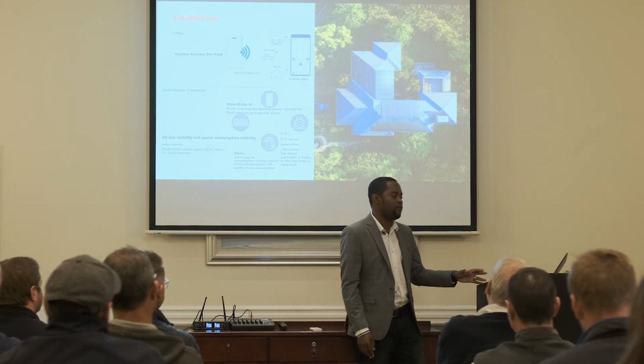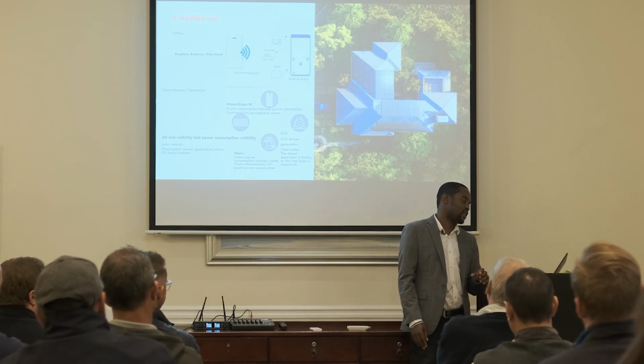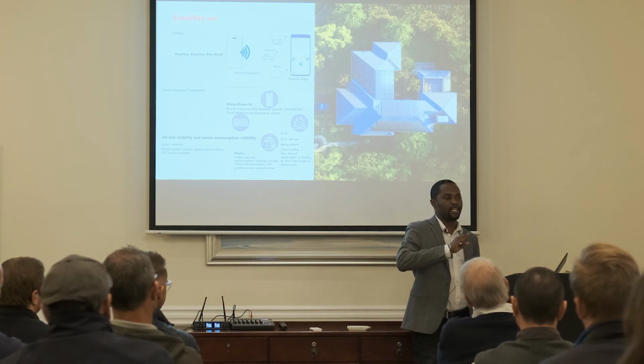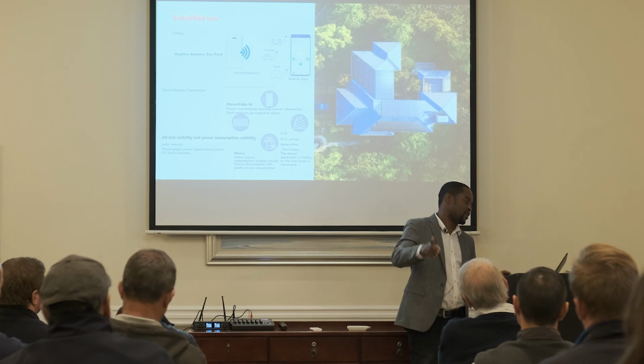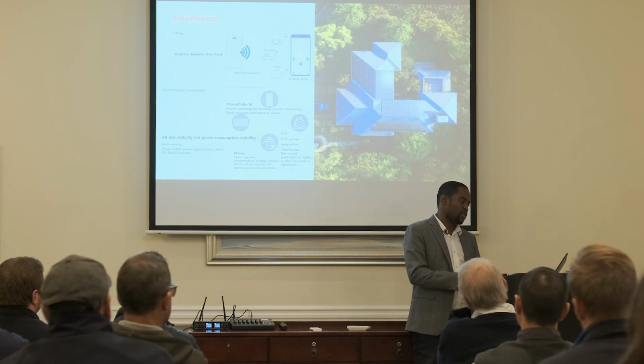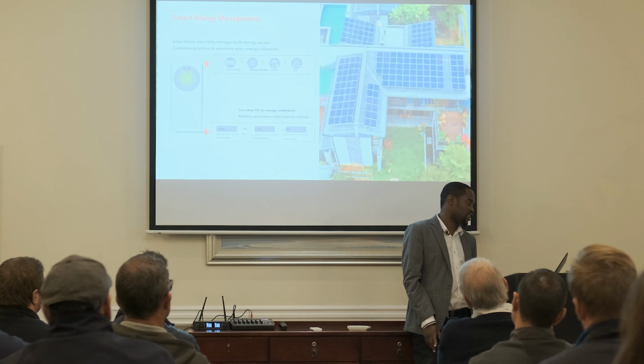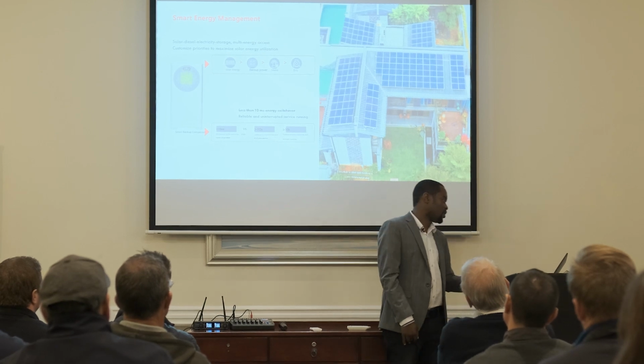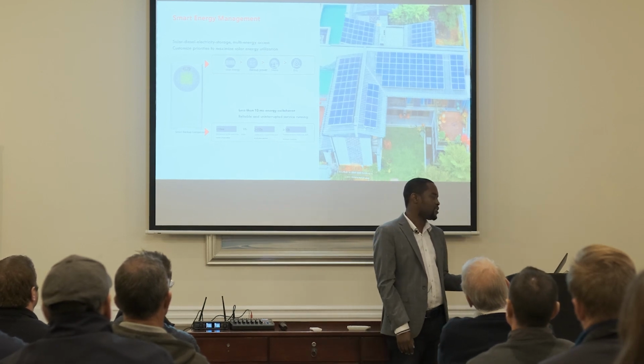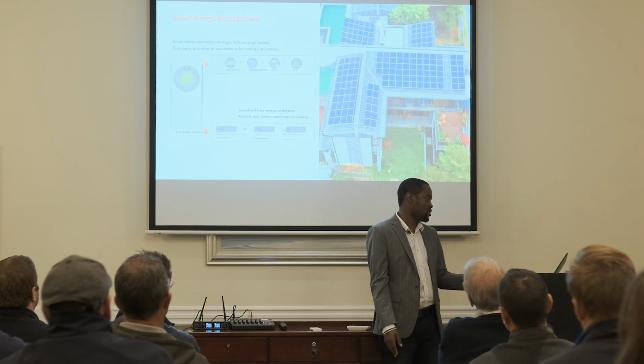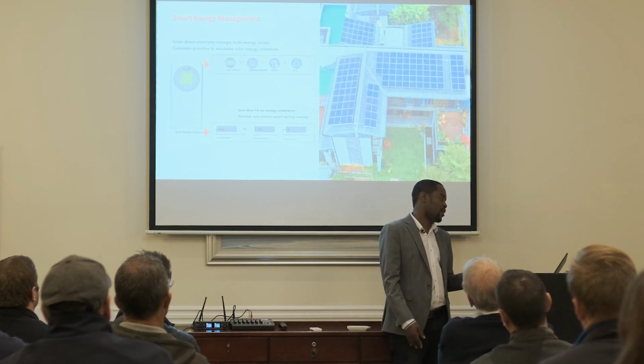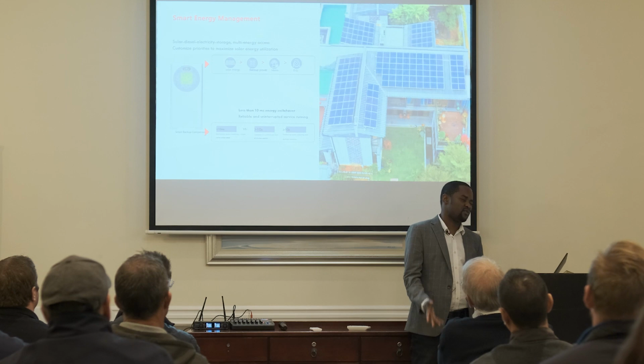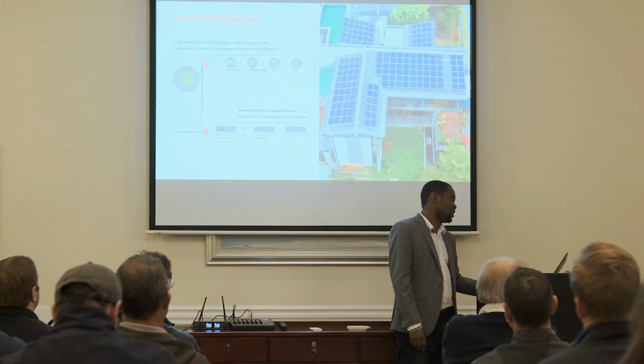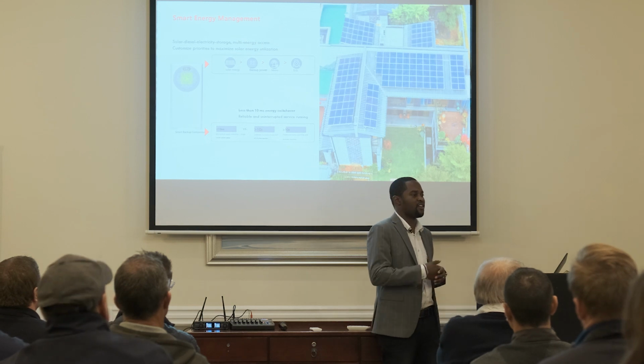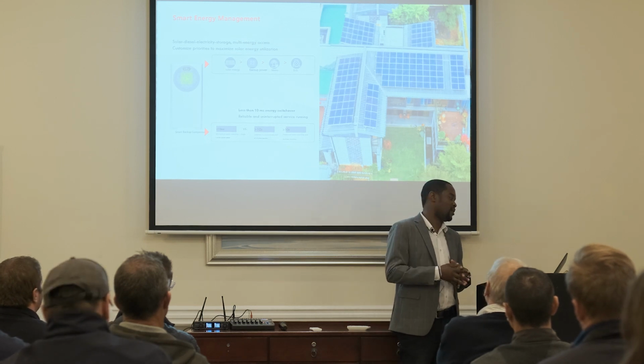When your batteries are full or they've reached a certain percentage that you would have set, the inverter can send a signal to the generator to stop it. So this is the genset integration that we have on the system. The system has got smart management where you configure the work mode. You prioritize the source of power. So the most economic one, you can actually do it the way you want. You can customize it. But the most economic one definitely is when the sun is available, you want to charge and use PV.